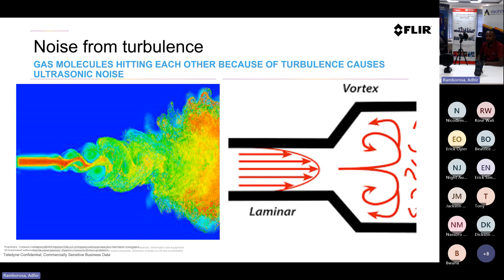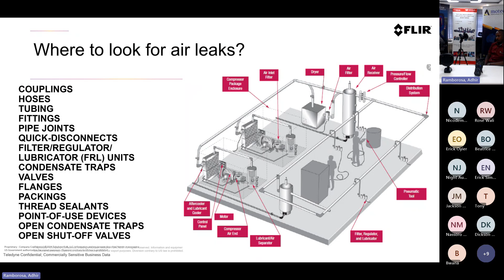If we look at a typical plant that's got compressed air, you basically have a compressor as your starting point, and quick release or point-of-use devices, quick coupling valves at the end. But in between, there's quite a bit, isn't there? You've got tubings, quick joints, valves, flanges—quite a few points, and these are all possible failure points. Using the SI2 camera, you can pick up if you've got any leaks of the smallest scale on those points.